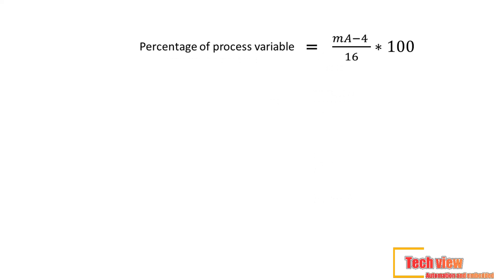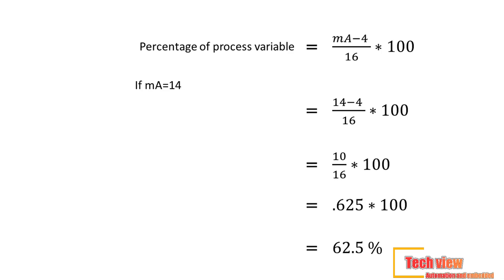On the other hand, if we know the milliamps and need to find the percentage of process variable, we have another formula: percentage of process variable equals milliamp reading minus 4, divided by 16, times 100. For example, if the milliamps reading is 14 mA: percentage of process variable equals 14 minus 4, divided by 16, times 100. That means 10 divided by 16 times 100, equals 0.625 times 100, equals 62.5%.